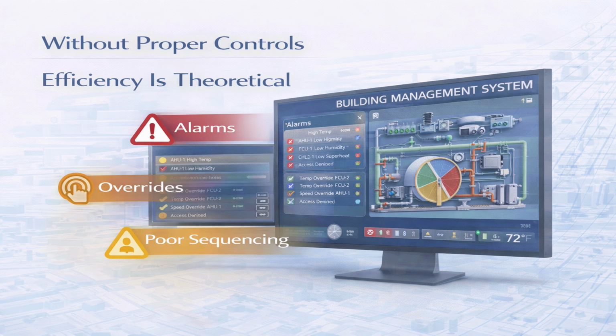When this happens, operators lose confidence in the system, and the building quickly moves away from its intended operating strategy. This is why unit selection must always align with the control philosophy. Capacity modulation, airflow control, valve behavior, sensor placement, and sequencing logic all need to be considered together, not in isolation. BMS integration should not be treated as a separate stage. It must be part of the selection and design decision from the very beginning. When equipment capabilities and control strategies are aligned early, the system operates smoothly, efficiently, and predictably over the entire life cycle of the system.